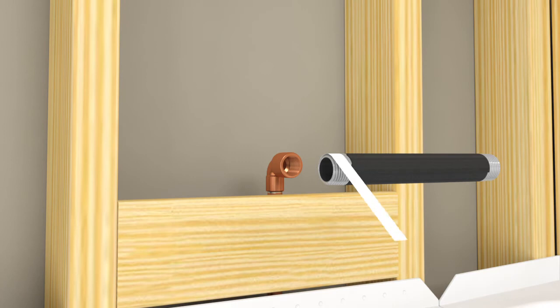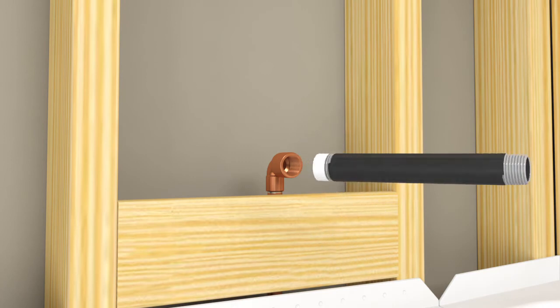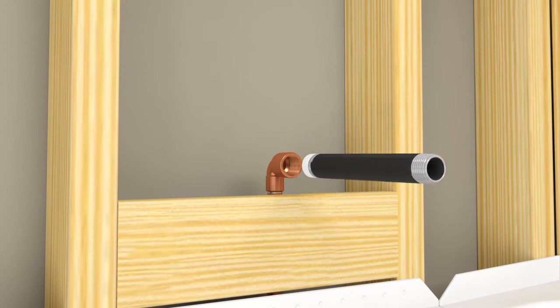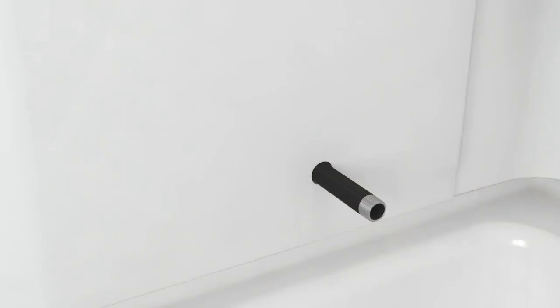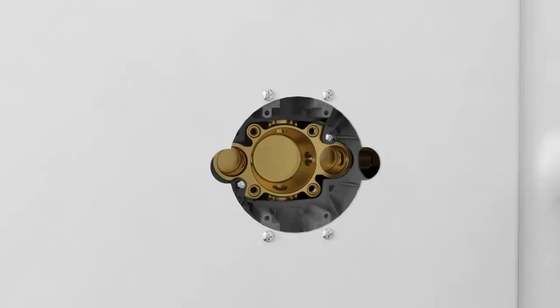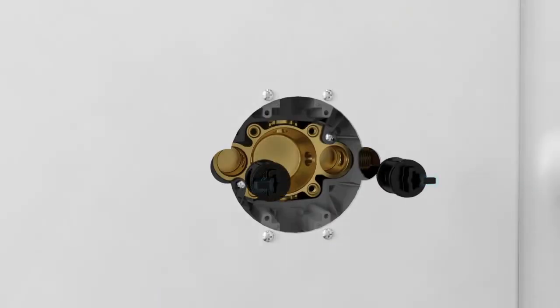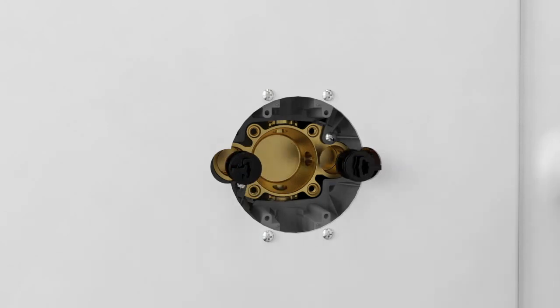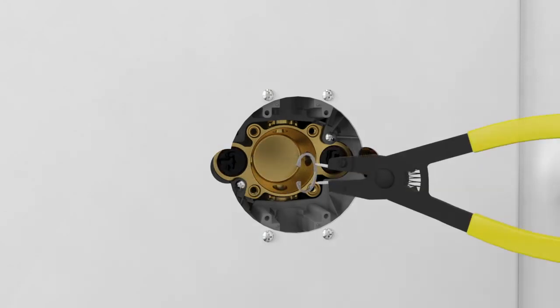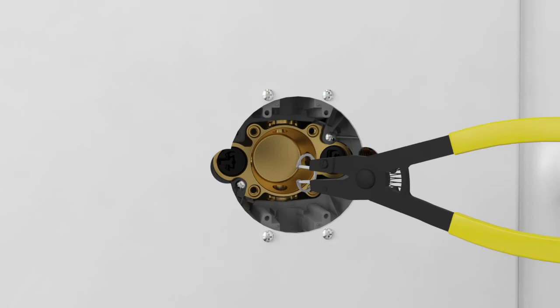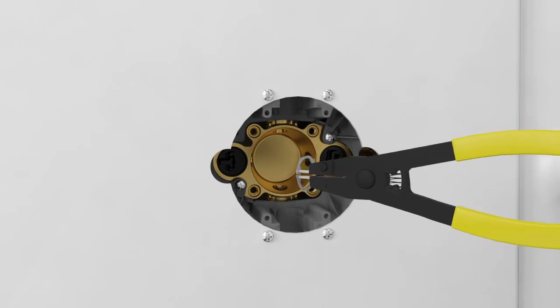Install temporary nipples in the shower and bath spout elbows. Be sure to apply sealant tape to all threaded connections. If your valve has stops, orient the tabs on the stops to the outside of the valve body and install the stops. Install the snap rings to the stops.